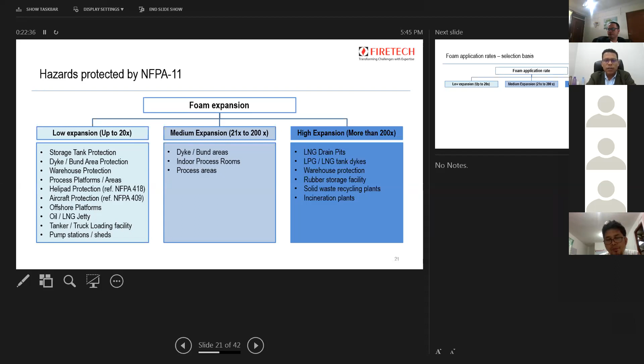Now, how do you go about foam application rates? The whole approach for designing a foam system first starts from the application rate. How much foam are we going to apply in the enclosed hazard or the hazard under consideration? When a designer is designing a low expansion foam system, the amount of foam to be applied is called the foam solution application rate, which is either in LPM per square meter or in GPM per square feet. Then the second step is the fuel type, whether it is hydrocarbon or a polar solvent. And the third factor which defines the foam application rate is the flash point of the fuel. NFPA 11 in fact defines different application rates based on the fuel and its flash point, based on which the foam system is designed.